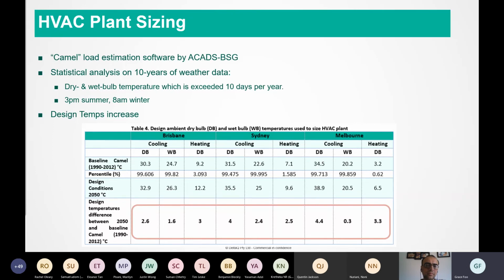But the main takeaway is that all of these design temperatures have increased, which means that if you were to use a future climate file to size, or weather data to size your HVAC plant, you would really be using a larger HVAC plant capacity.